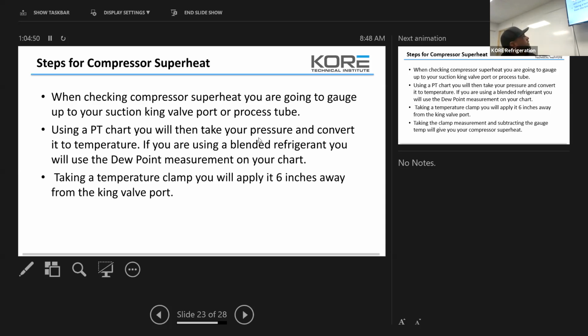Using a PT chart, you'll then take the pressure and convert it to temperature. If you're using a blended refrigerant, you can use a dew point measurement on your chart. So remember the difference between dew and bubble. Bubble is going to be subcooling. Dew is going to be superheat. If you're dealing with a 3-component or a 4-component, and I know there are even higher component blends now. I think I heard 448 was a 6-component. So 6 different components in that refrigerant. That's why the glide's so wide. When you're dealing with a blended refrigerant, you're going to have a glide. So you have to make sure you're looking at the right value on that PT chart for what stage the refrigerant's in. That's why the glide matters.